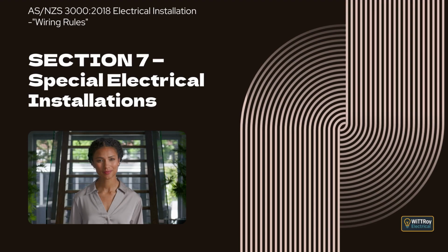Clause 7.2.5.2.2, Segregation of cables. This clause explains that conductors supplying fire pumps and fire pump control equipment must not be enclosed with conductors of different safety services or with conductors of any other wiring system. It explains how effective segregation can be achieved using separate channels, compliant wiring systems, physical separation within switchboards, and by ensuring that conductors of different safety services are not combined within the same multi-core cable.